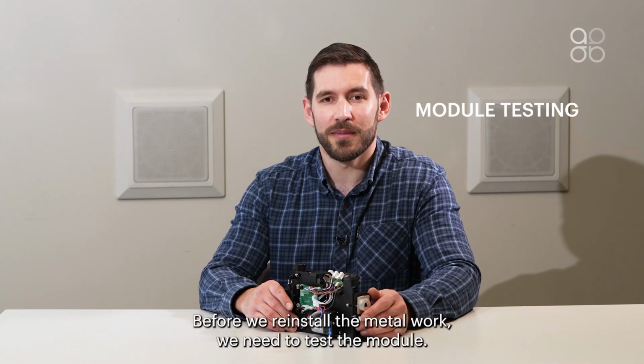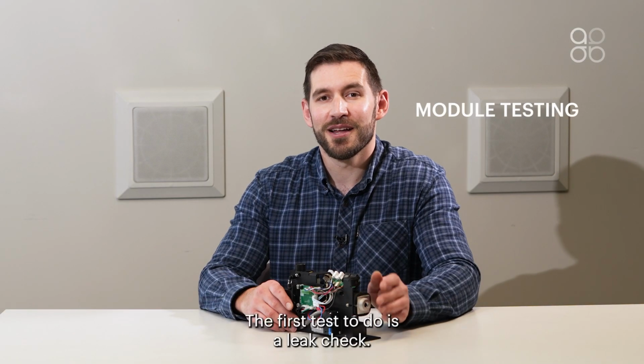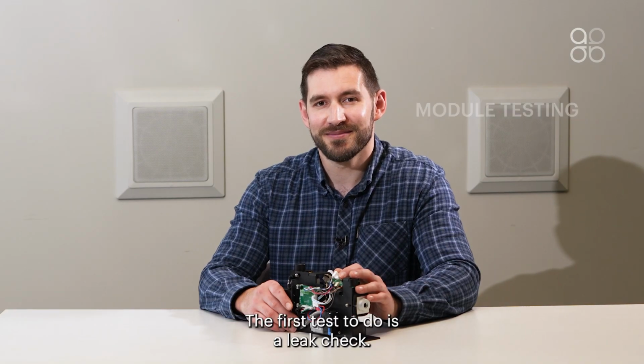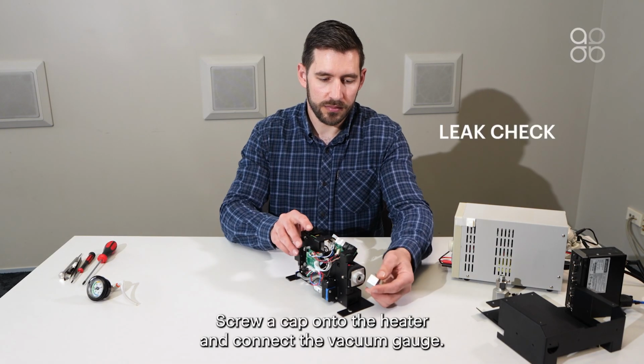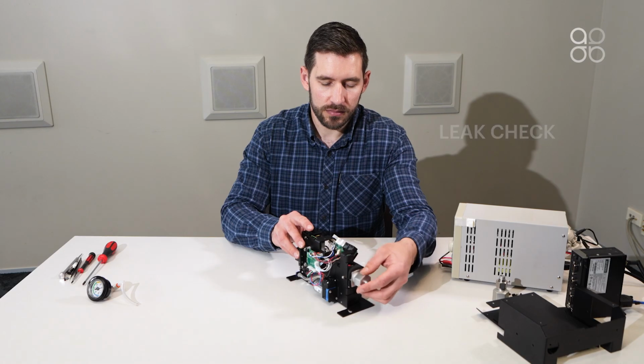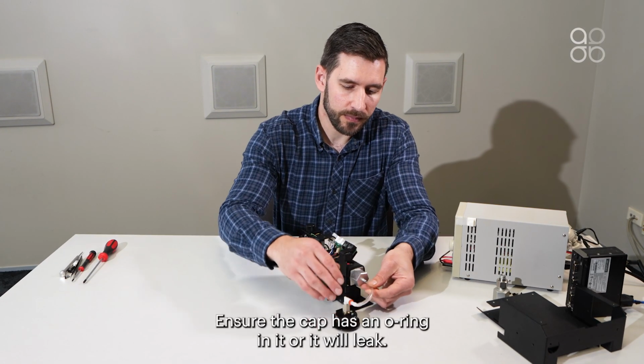Before we reinstall the metalwork, we need to test the module. The first test to do is a leak check. Screw a cap onto the heater and connect a vacuum gauge. Ensure the cap has an O-ring in it or it will leak.